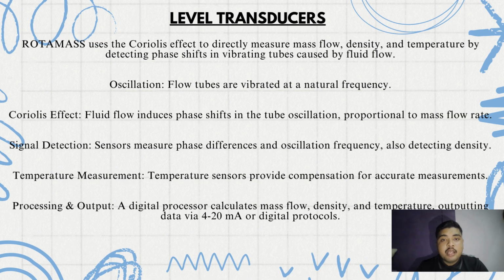Flow tubes are vibrated at natural frequency. Second, Coriolis effect. Fluid flow induces a phase shift in the tube oscillation proportional to mass flow rate. The third, signal detection. The sensor measures phase difference and oscillation frequency, also detecting density. And the fourth, temperature measurement. The temperature sensor provides compensation for accurate measurement. And the last one, processing and output. A digital processor calculates mass flow, density, temperature and outputs data via 4 to 20 milliampere or digital protocols.